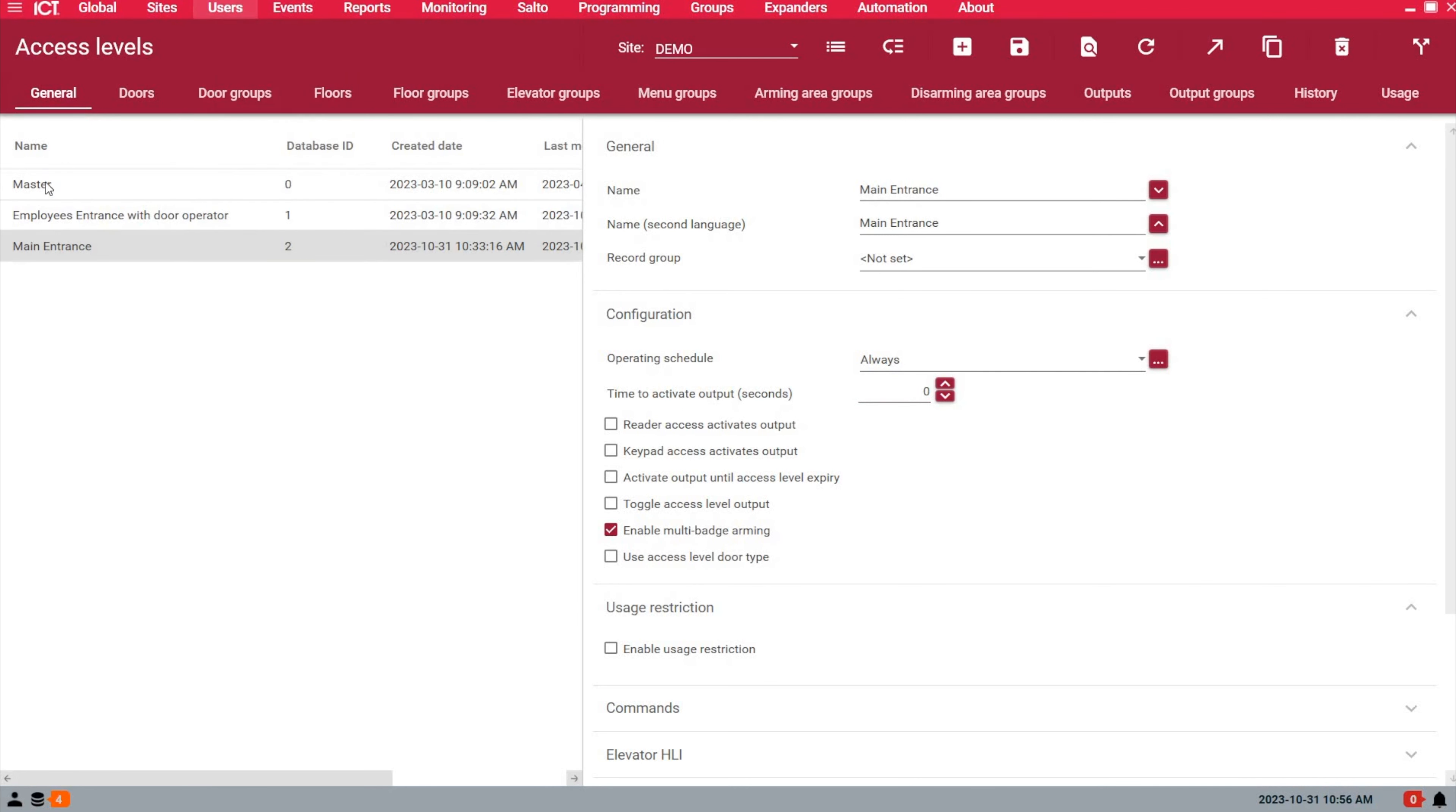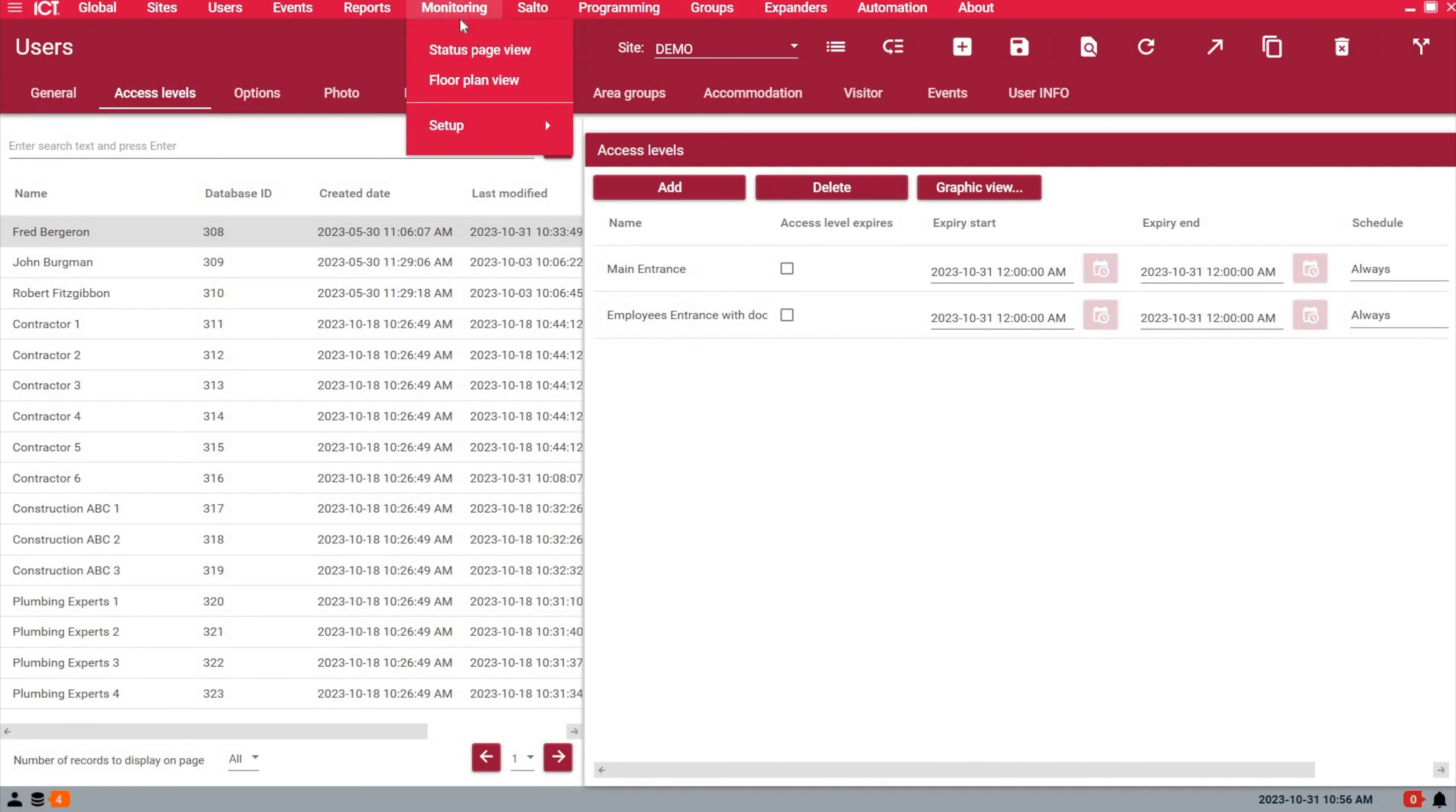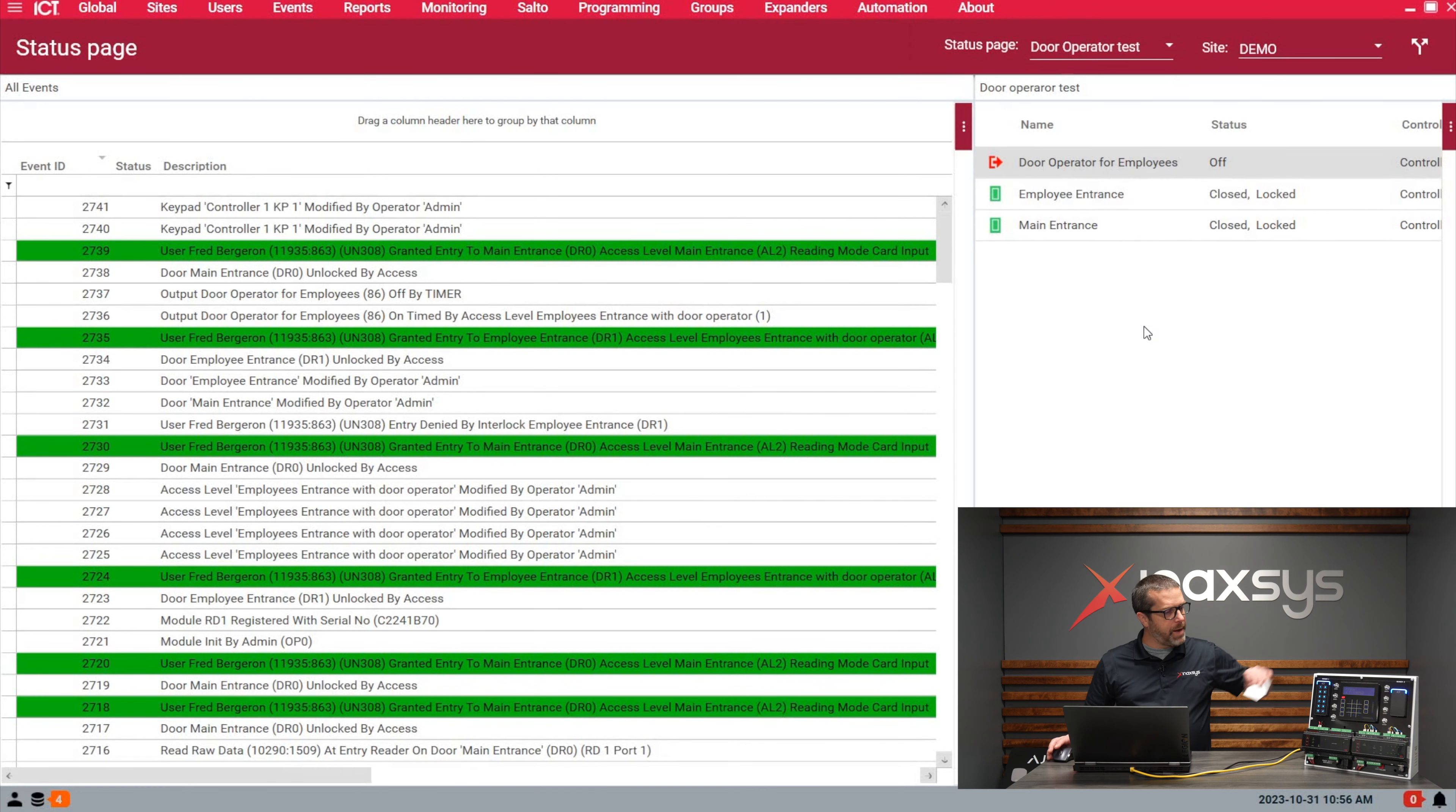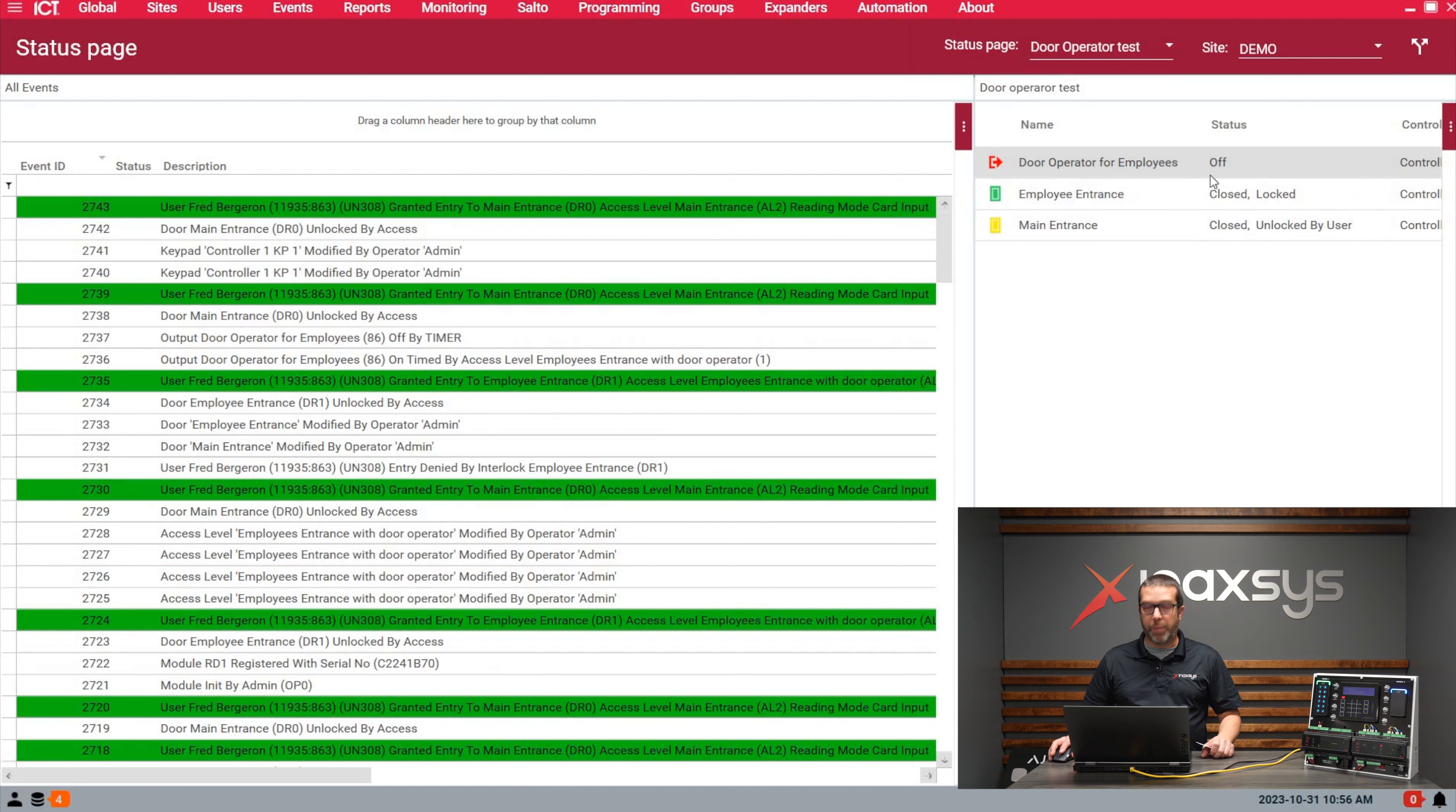The last step is to pick a user and assign the two access levels. If I go to the monitoring page for this test, you see the door operator output is off. If I badge on the main entrance, the main entrance will unlock and then lock again, but the output does not trigger.